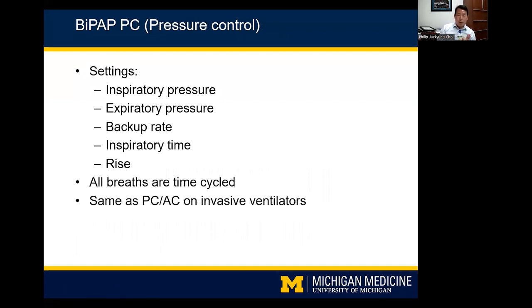Over time, NIV modes have become more sophisticated. Pressure control BiPAP has similar settings — inspiratory pressure, expiratory pressure, backup rate, inspiratory time, rise — but without cycle sensitivity. All breaths are time-cycled regardless of whether patient- or machine-triggered. This is equivalent to PC/AC on invasive ventilators; on the new Trilogy EVOs it's actually called PC/AC. The difference between ST and PC is important: both have pros and cons, and understanding the distinction is essential.